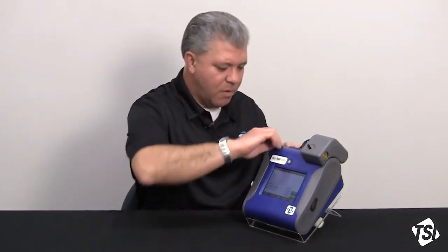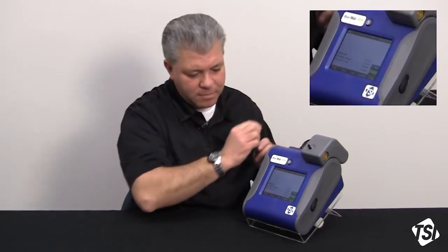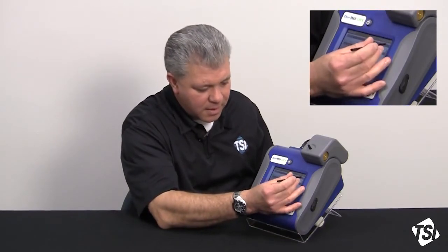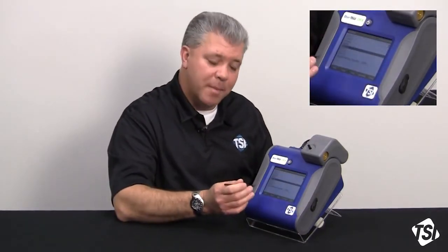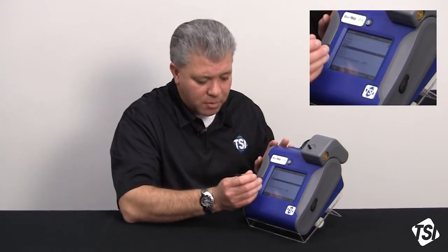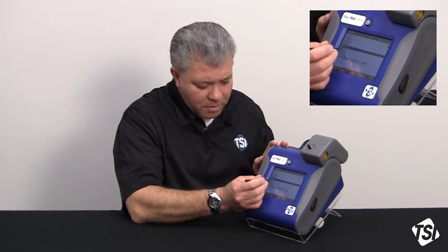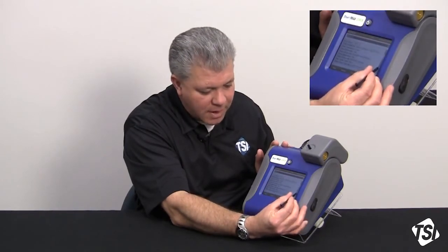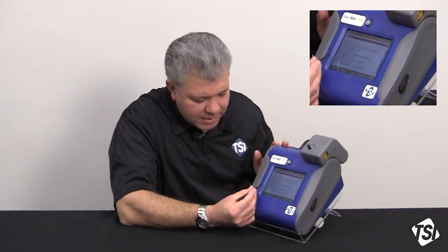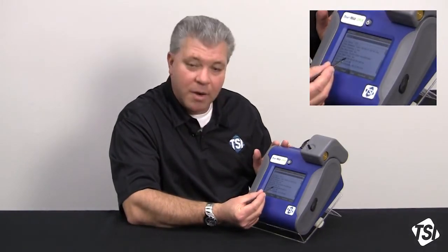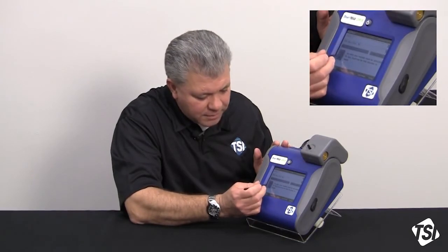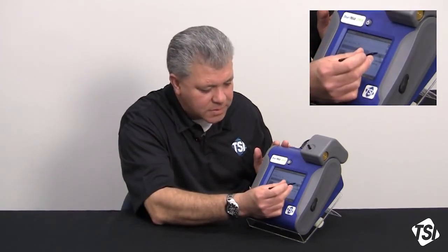Now, what we do is we go over to the setup menu, or excuse me, the run mode menu. Click on that, come up to a logged program. You set this through the logging programs, not the manual program, only the program log modes. So I'm going to select one of the program log modes. I'm going to scroll down to the very bottom, and basically here, AutoZero module on or off. I'm going to select that, and I'm going to toggle the down arrow key to turn it on and save that.